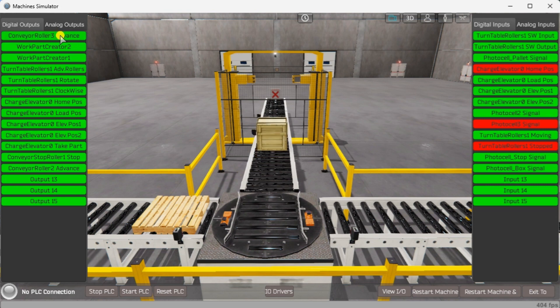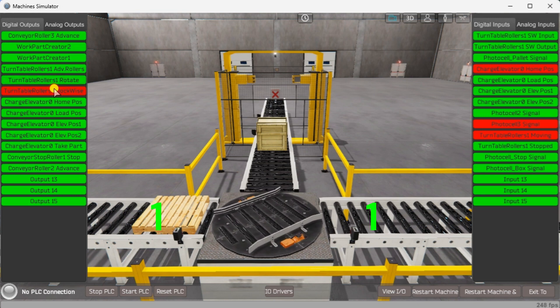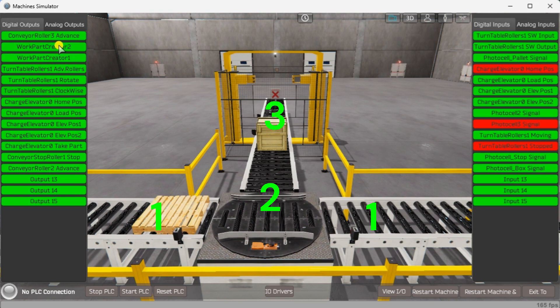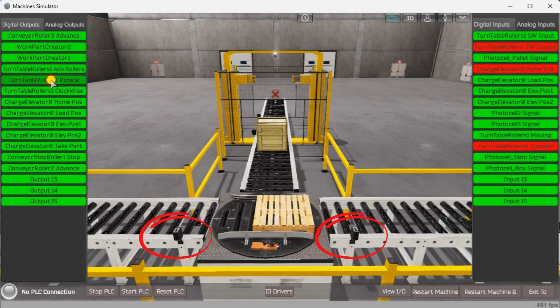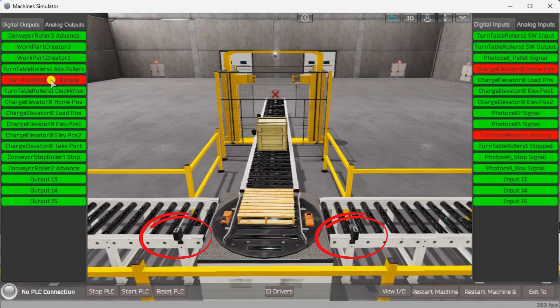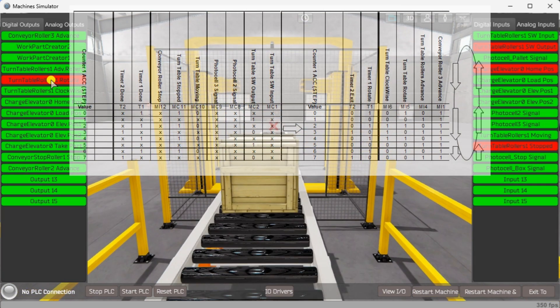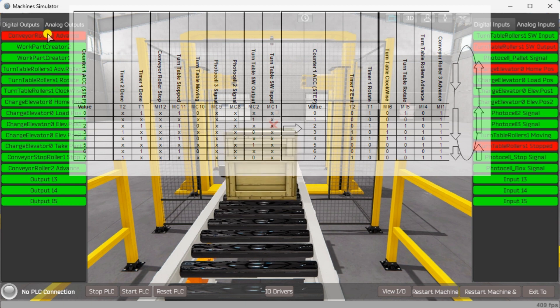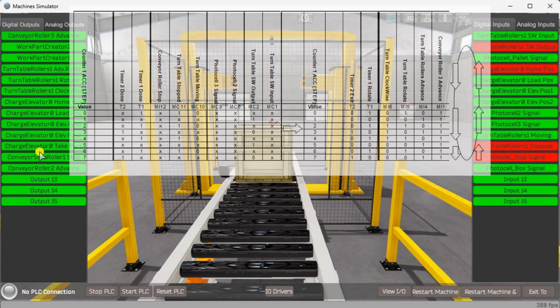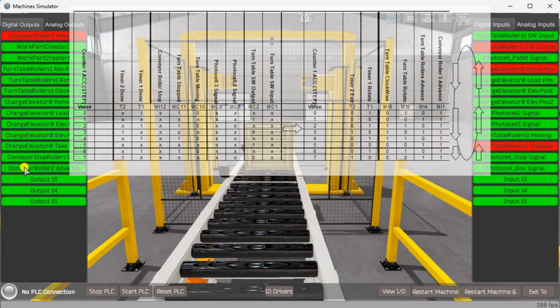Our DoMore PLC palletizing conveyor program will break down into three components: the conveyor controlling the box and skid, the turntable, and the elevator. The box and skid creation will happen if the end sensor does not see the item, ensuring a box and skid are always at the end of the conveyor ready for the turntable. Our sequence table for the turntable will show input signals on the left and output signals on the right. The value of the counter is shown with each step. We can move to the next step by looking at counter value zero, with timer one done and the turntable stop signal. The steps are repeated for each counter value until the last step of seven, which resets the counter back to zero.